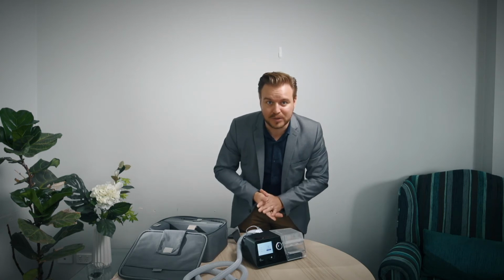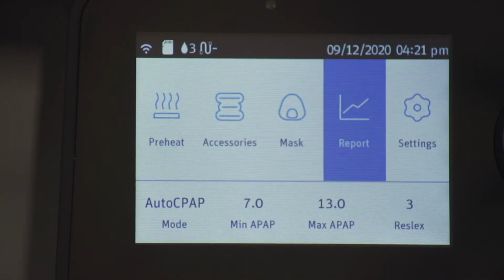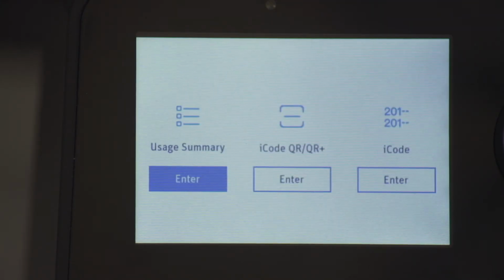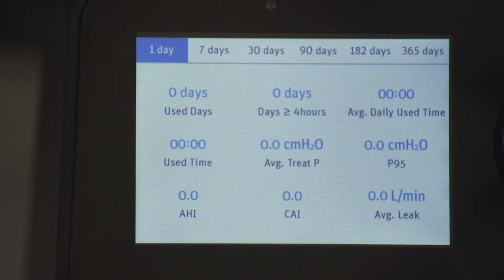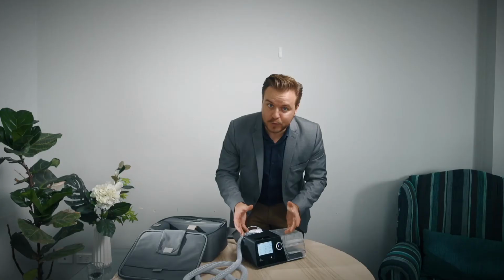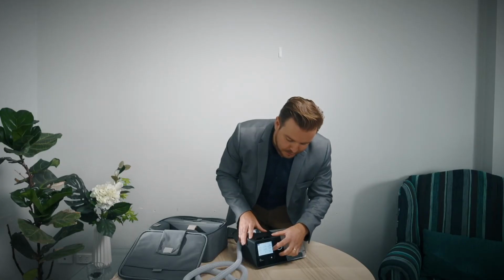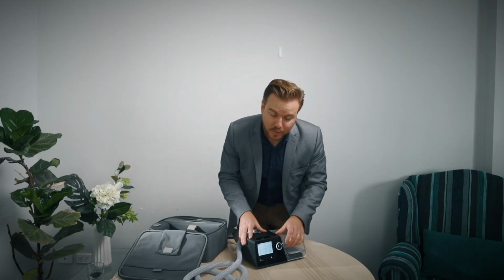It'll give you the thumbs up, so you know you don't have to change your cushion or anything like that. In the reporting options, the most basic way of viewing the data on this device is through a usage summary that's generated on screen. In here, it'll give you some compliance data, some basic statistical information, so your apnea-hypopnea index, any leaks that's occurring. If you're using an automatic pressure machine, it'll tell you your 95th percentile value as well.